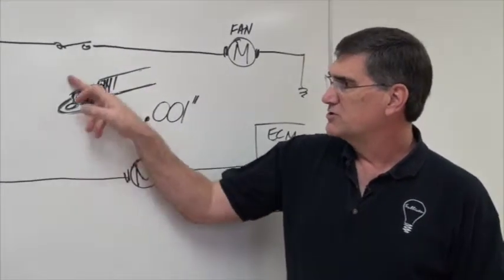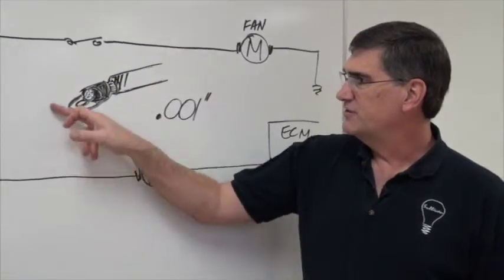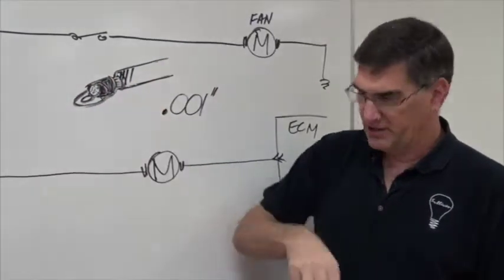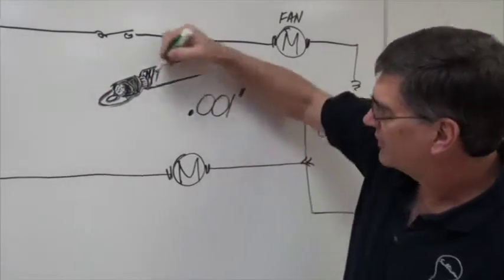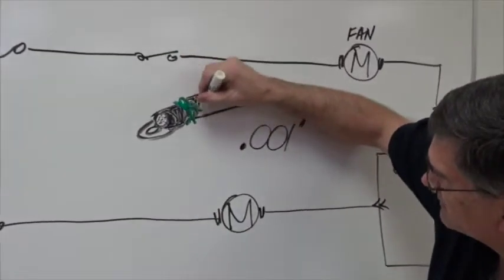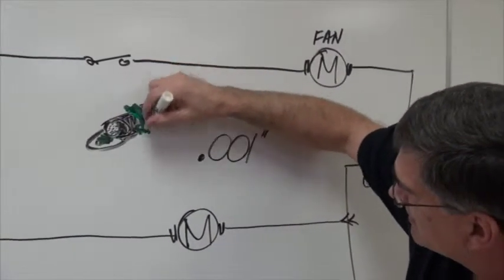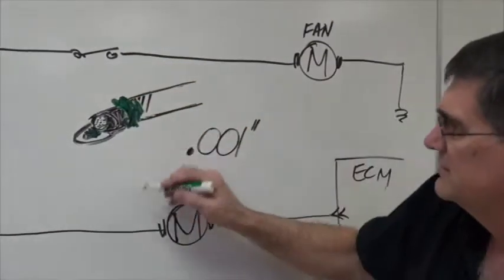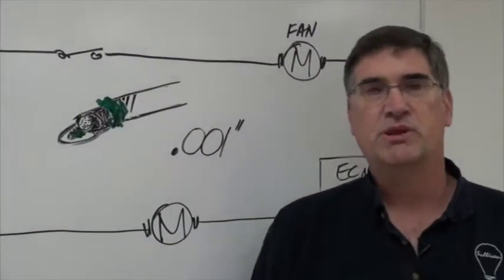The corrosion that occurs on a cable is a thousandth of an inch thick. Anything that's green, anything that's green at all, is not to be cleaned, you replace it. You don't clean green, you replace it.